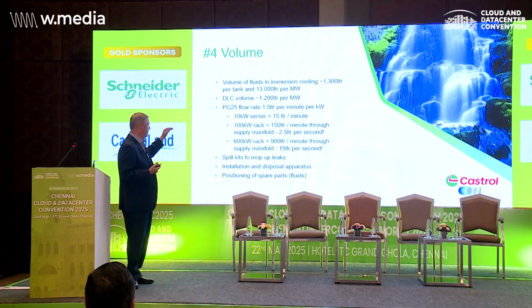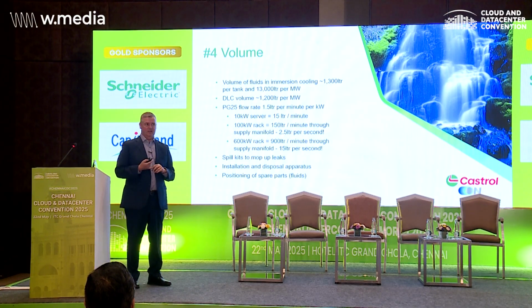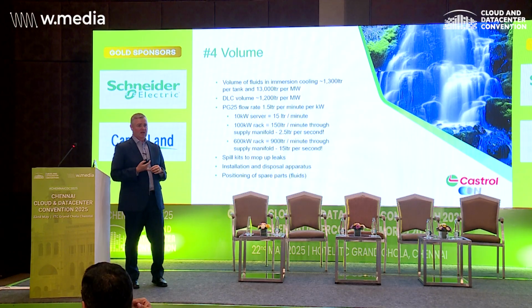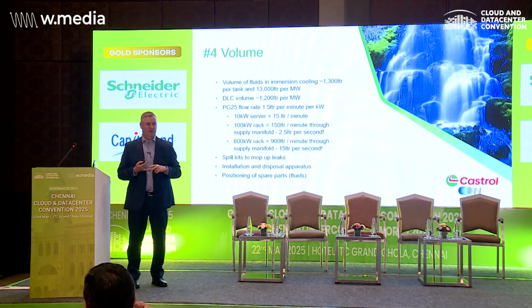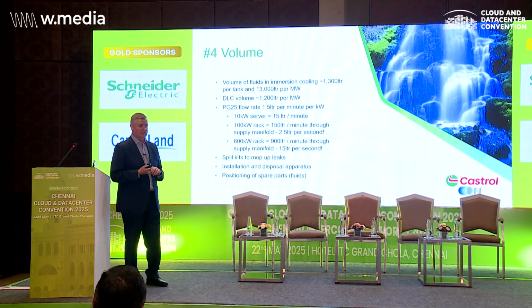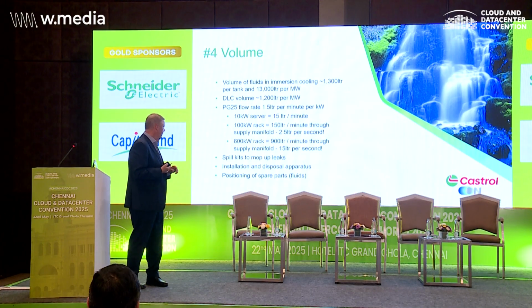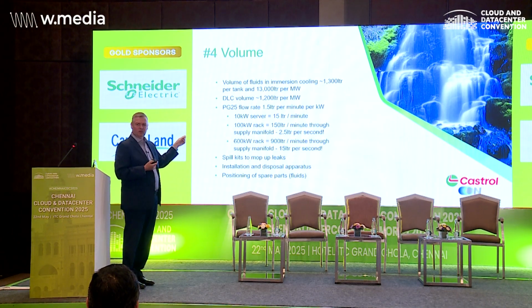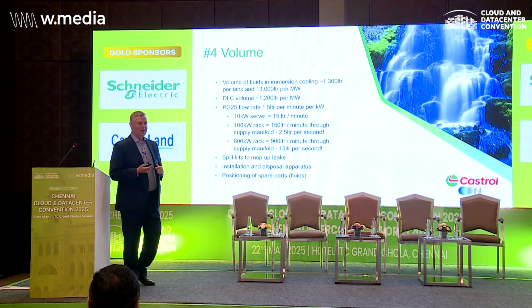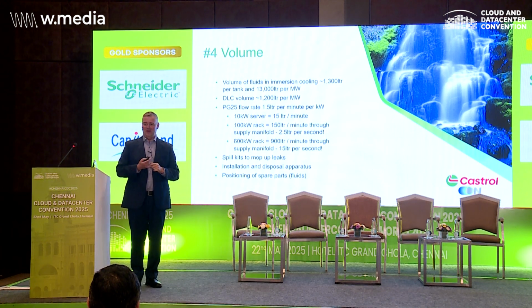But then we start going into a 100 kilowatt rack, that's 150 liters per minute, 2.5 liters per second. And with the latest announcements from Mr. Huang and NVIDIA of 600 kilowatt racks, we're now potentially talking 900 liters per minute, or 15 liters per second. So all you data center operators, enjoy.